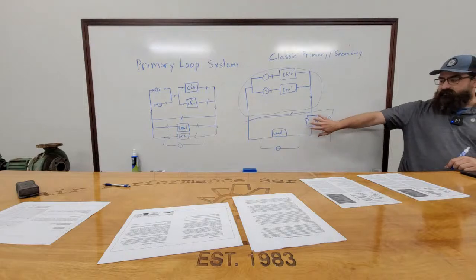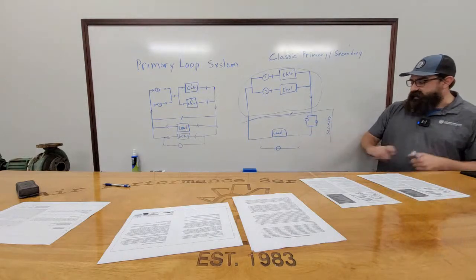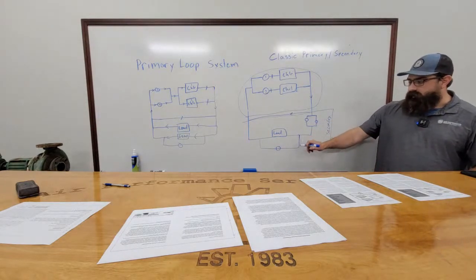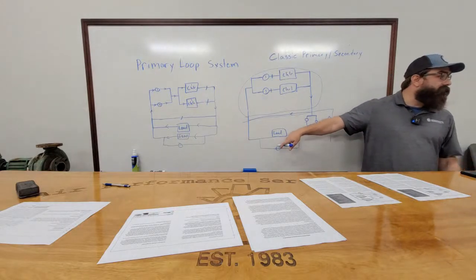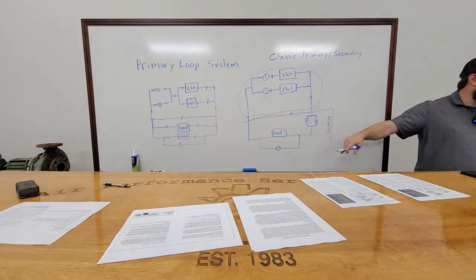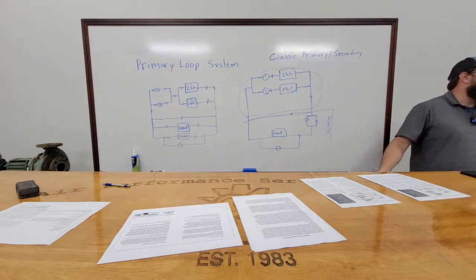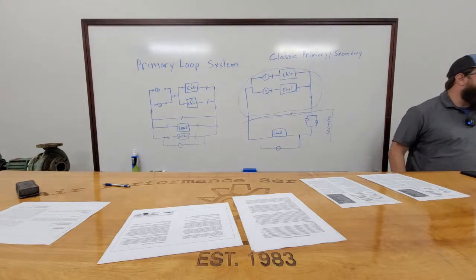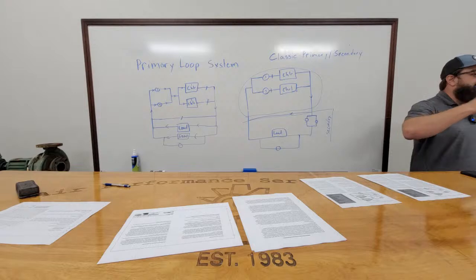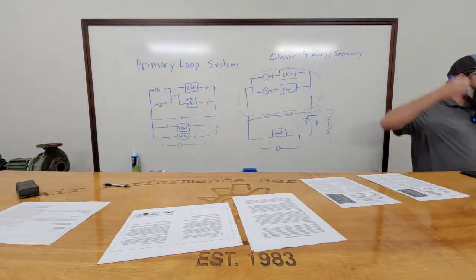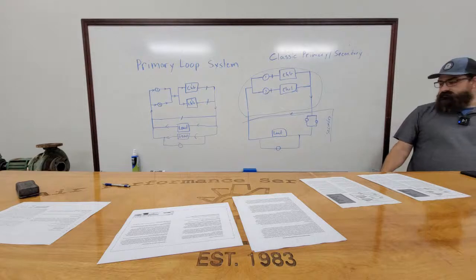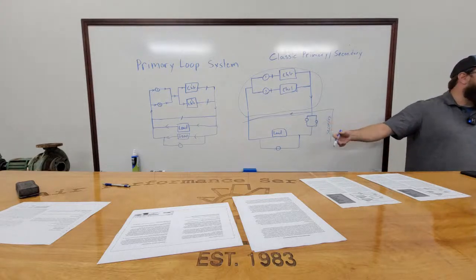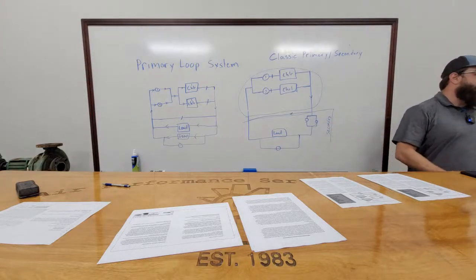Right. So we can modulate these pumps to maintain that differential. And then if they get down to a certain level, some systems have, very few, but some do have a secondary bypass loop on the primary. Secondary, but it's usually a three-way valve. They rarely have another valve that will open. Usually it's a three-way up at the top, or like the top two air handlers have a three-way valve. So you typically won't have a bunch of two ways and a bypass, but some buildings do.